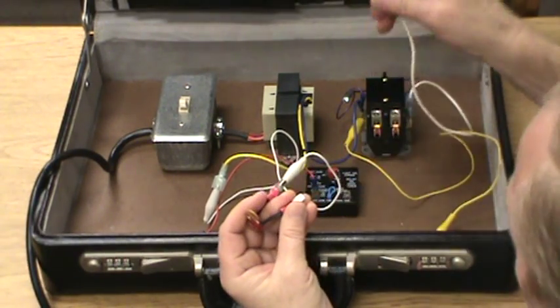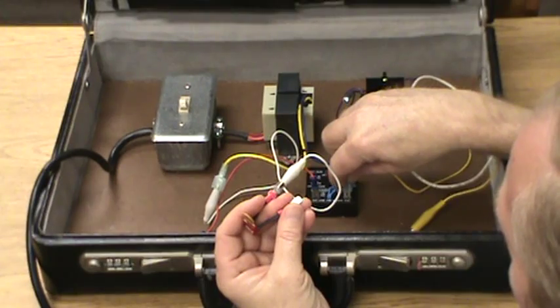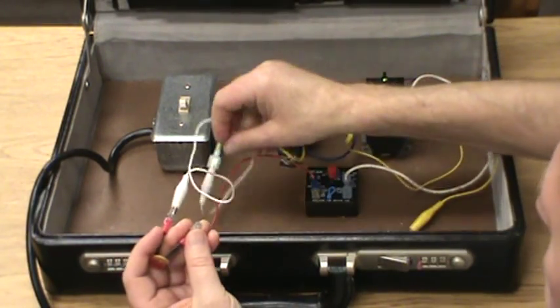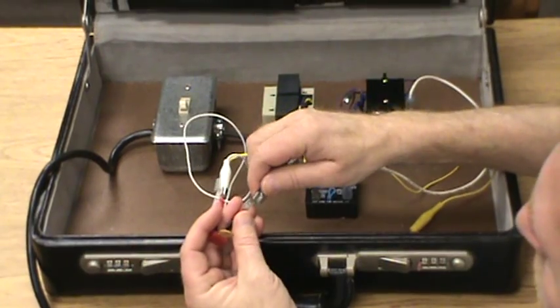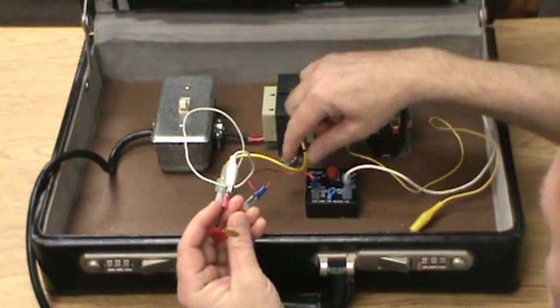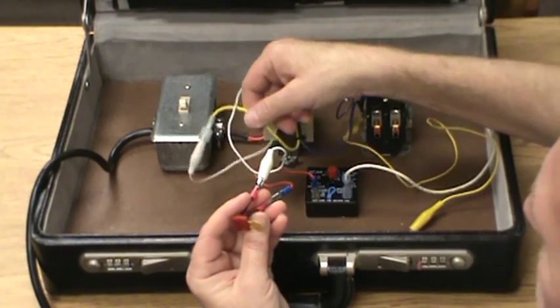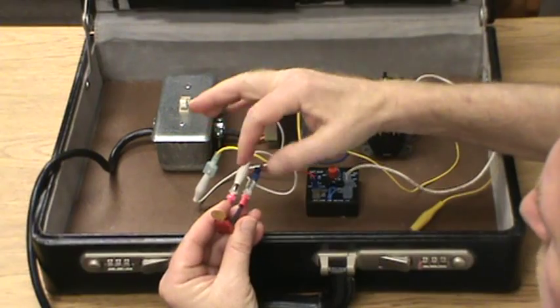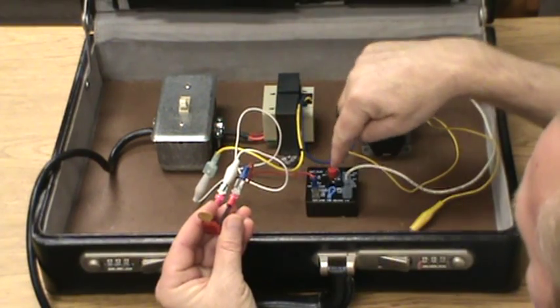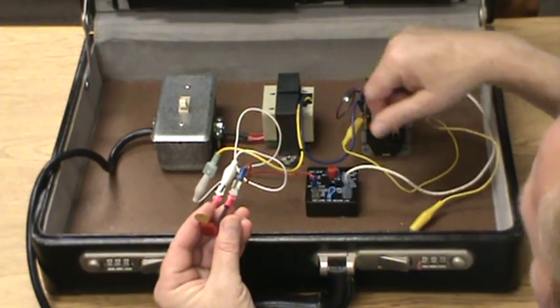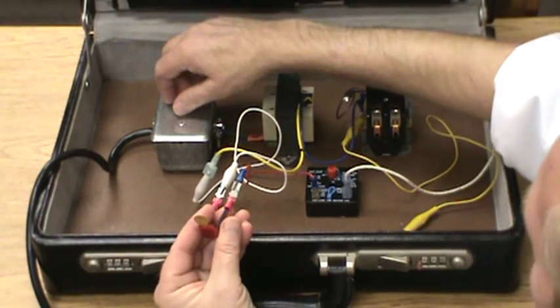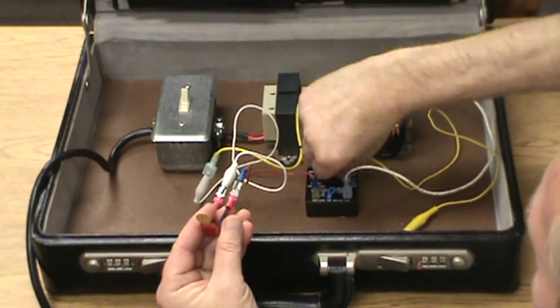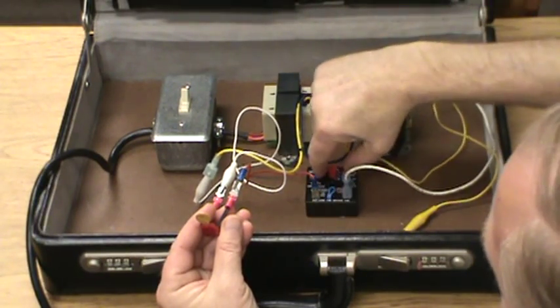I'm going to wire in this delay-on-make time delay. What we're doing is coming out of the transformer secondary, going to our protection - this resettable fuse - and then it's going through this time delay circuit here. I'll restore the power and advance this timer so it will bring on the contactor coil.